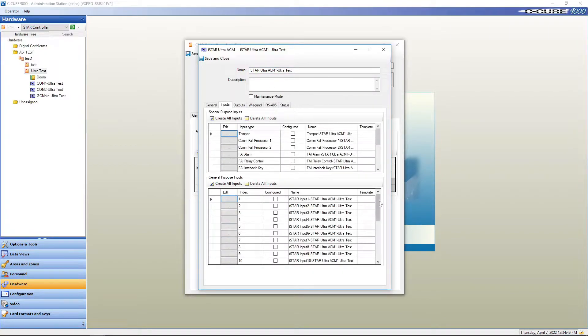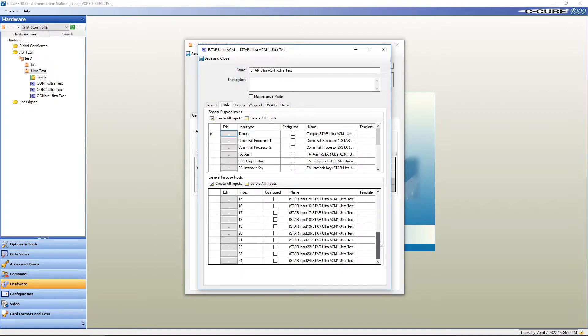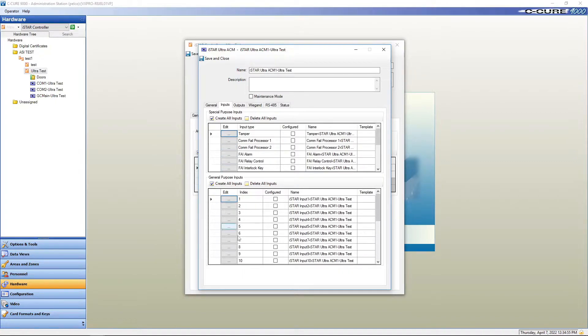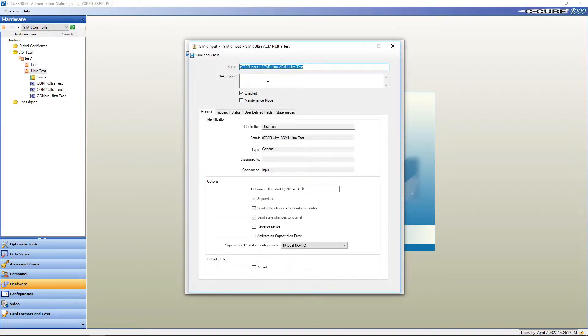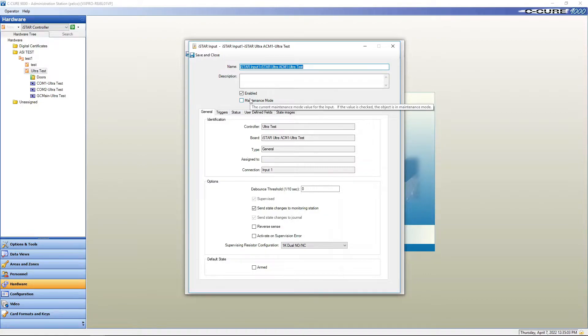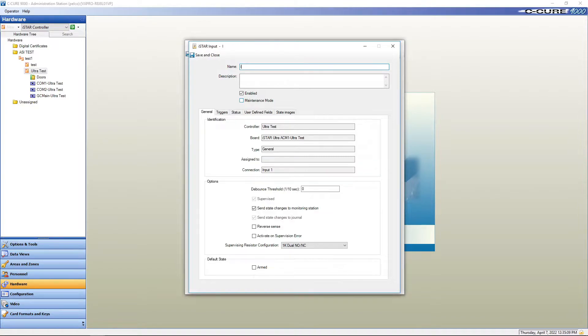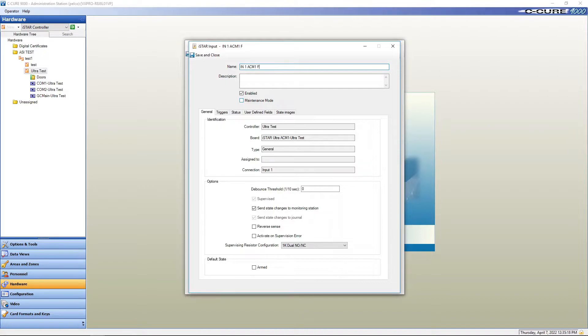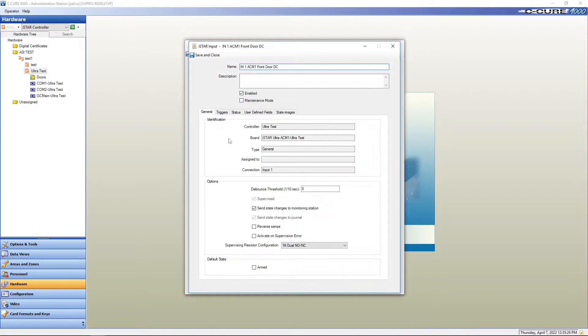24 inputs on an ACM board. We're going to start with number one, configure, edit, and we're just going to do a standard door with a door contact and a request to exit, one reader, one lock. So here, I like to go IN1, ACM one, we'll call this the front door, and then DC for door contact.